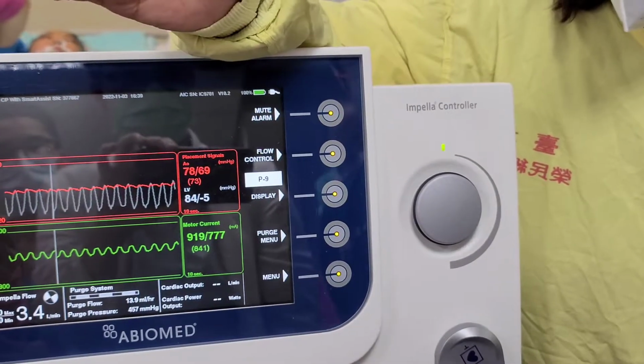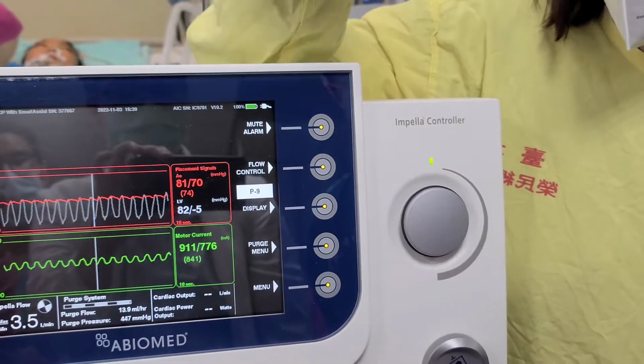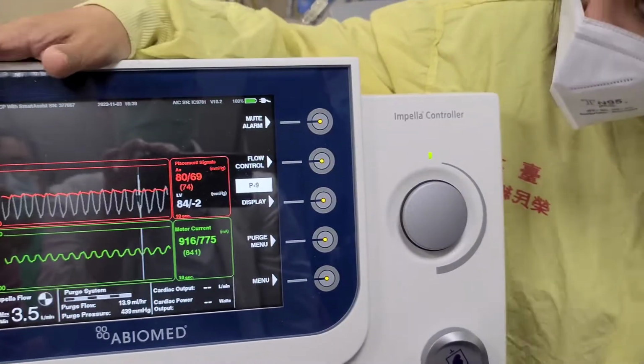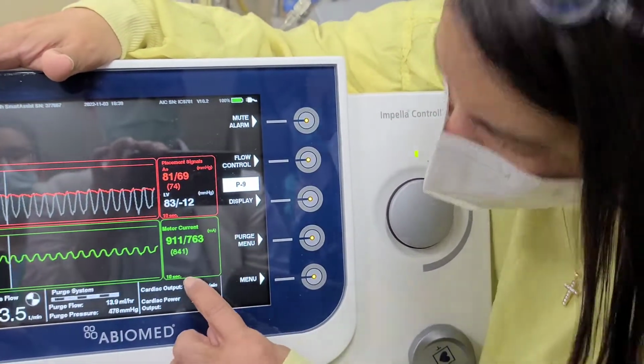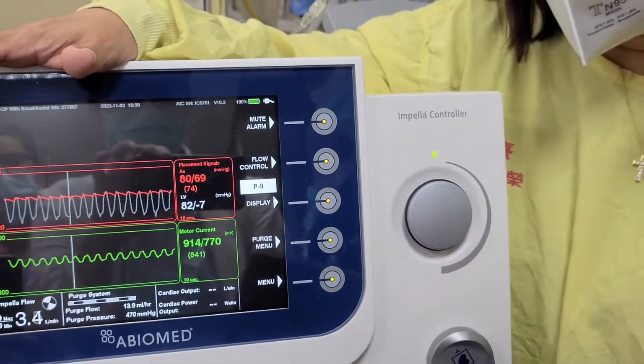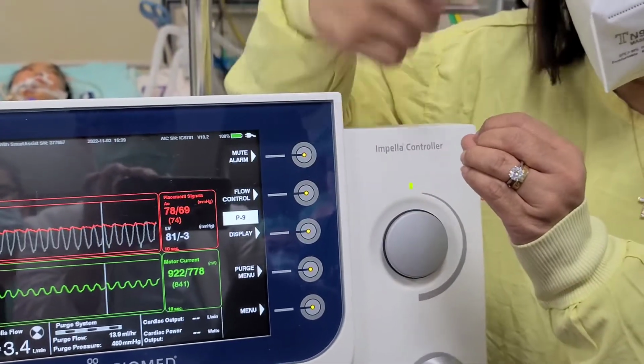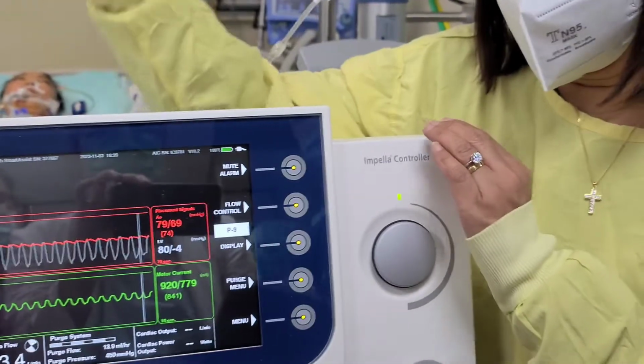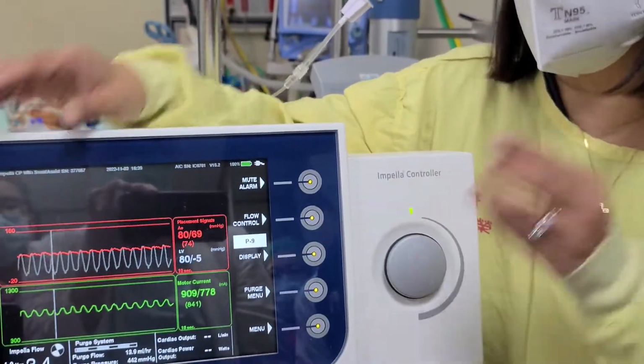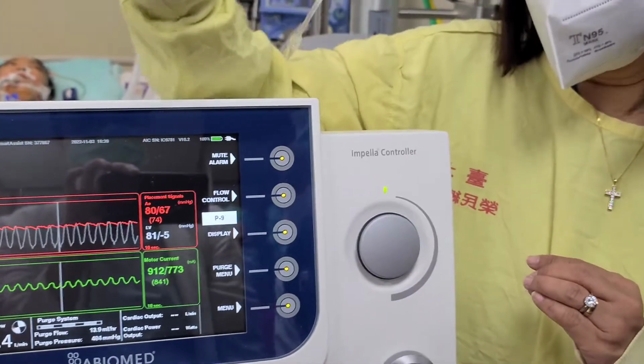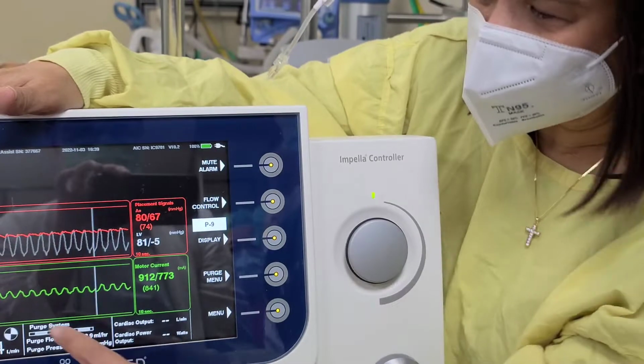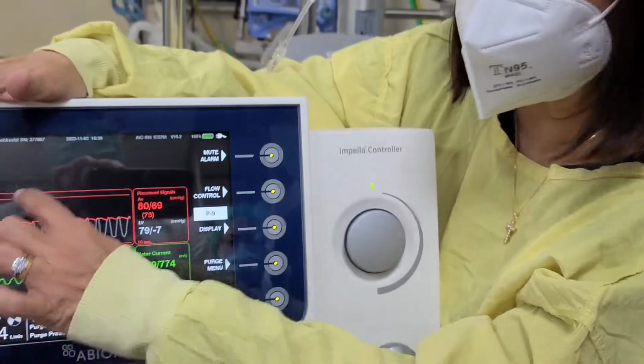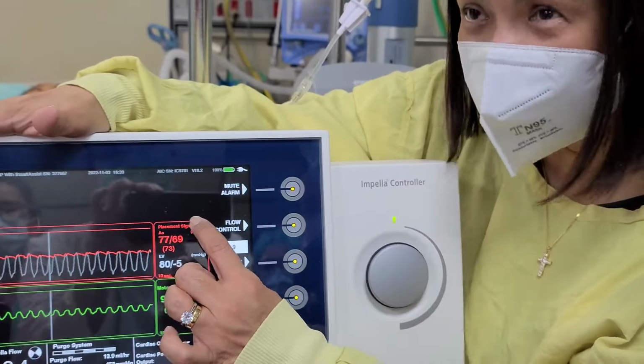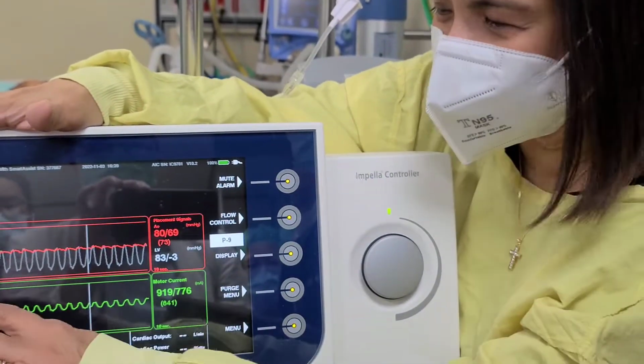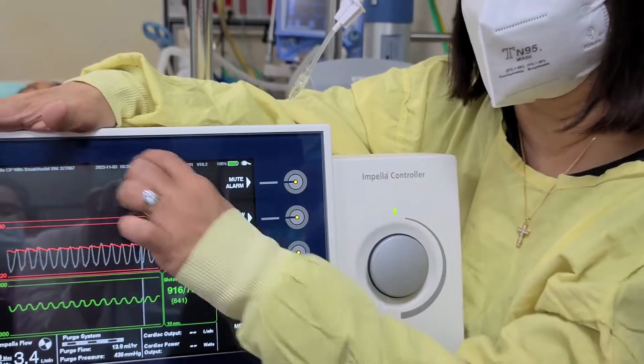Because the aortic valve opens and closes, the gradient between the ventricle and aorta changes. Motor current is measured in milliamps. It looks at how much energy is needed to spin the impeller at a fixed speed, and it changes depending on your gradient. So this shows the impeller is in the correct position, inlet in the ventricle, outlet in the aorta. If it slips out, you will see a flat motor current and only an aortic waveform. If it slips all the way into the ventricle, you will still have a flat motor current, but you will see a ventricular tracing. And you also have an alarm.